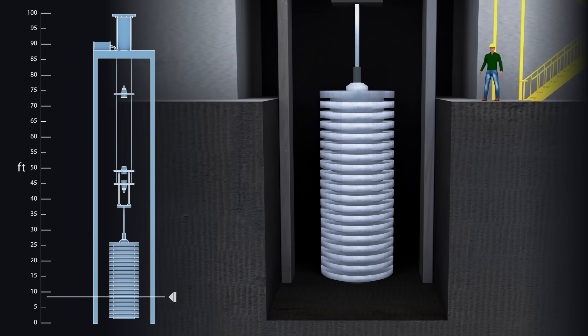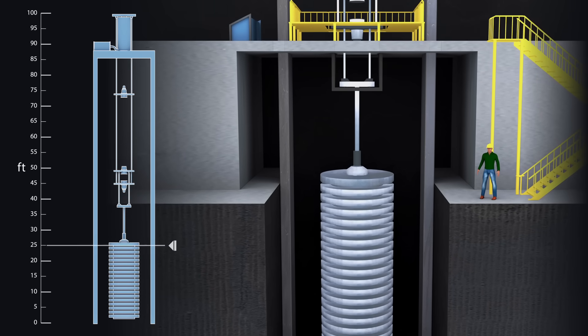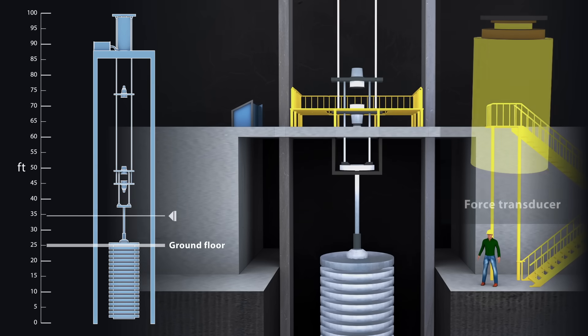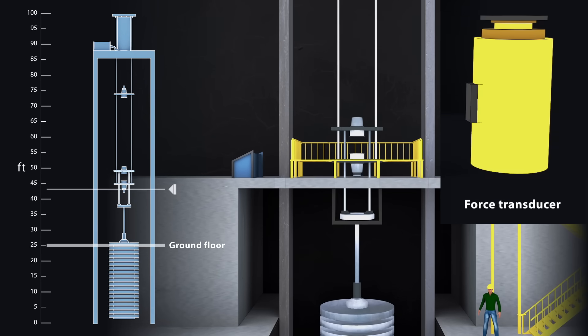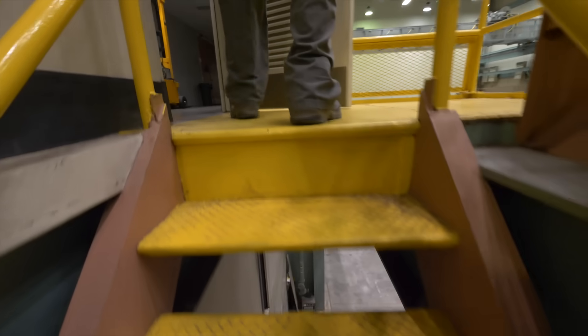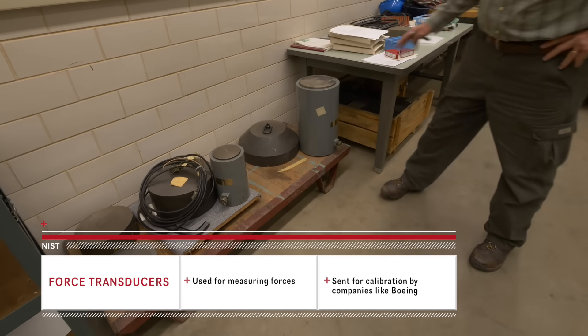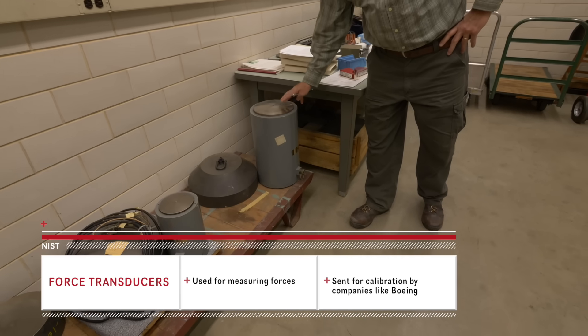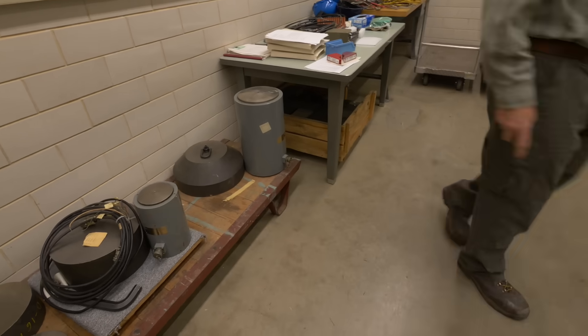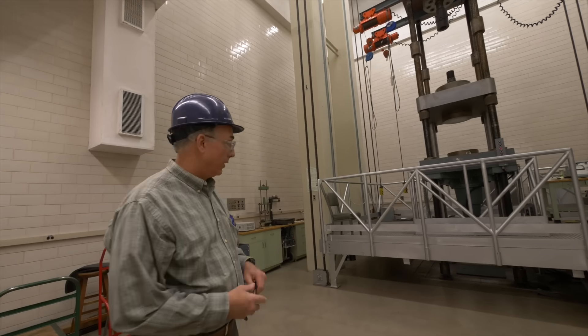The machine works like this. Below ground are 20 carefully calibrated masses. Their weight is used to calibrate force sensors, also called force transducers, in the lab upstairs. This is a 1 million pound capacity — 4.45 meganewton machine — and this one is 13.3 meganewtons, 3 million pounds force. This is the biggest machine of its type in the world, and obviously one of a kind.